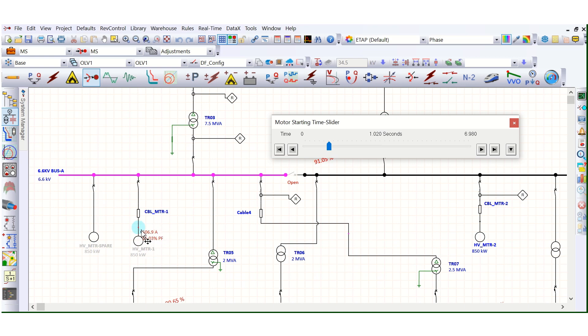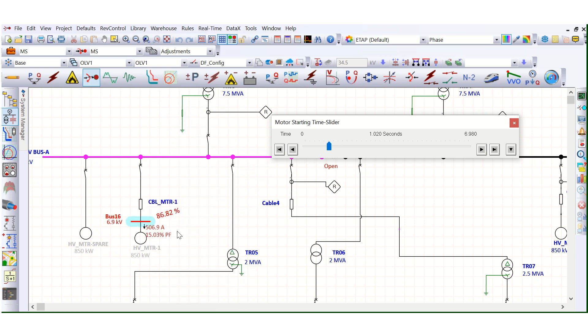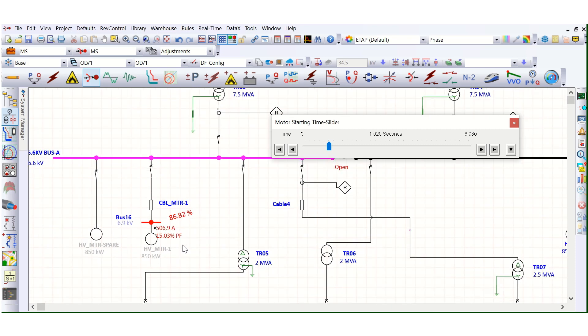So it is showing now. If you want to see here, the motor terminal voltage, you can change it to bus. So motor terminal voltage is 86.82%. And it is drawing 506.9 Ampere and starting power factor of 15.03%.